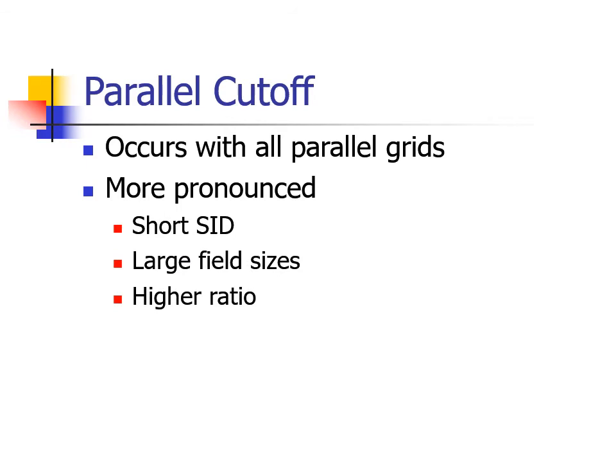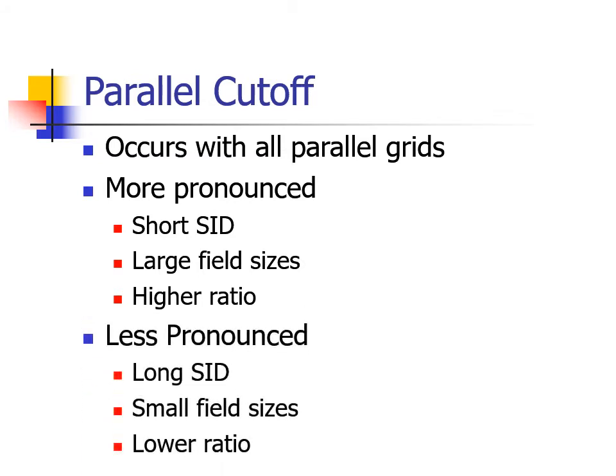So, one can expect that you will see some amount of cutoff on all parallel grids. The amount of cutoff will be more pronounced with short SID exposures, large field size, or higher grid ratios. The opposite of the above list will also produce less cutoff.